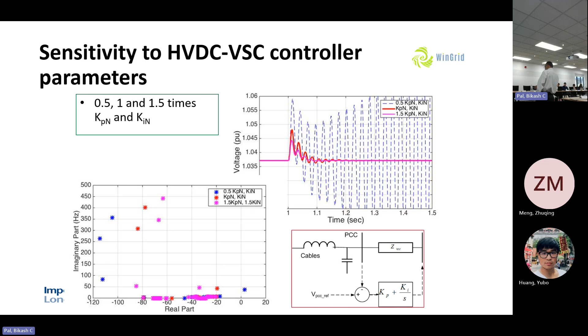So this happens. Another thing I wanted to show you is the grid side converter control bandwidth with PMSG. If we move the bandwidth from 5, 10 to 20, with 20 you see that the voltage is oscillating. So this is how the bandwidth works. That means if we make the grid side converter control a fast response, then the interaction between the collection side, the cable side, and the individual turbine side is encouraged. So sometimes making the grid side converter control slow may help rather than making it fast.